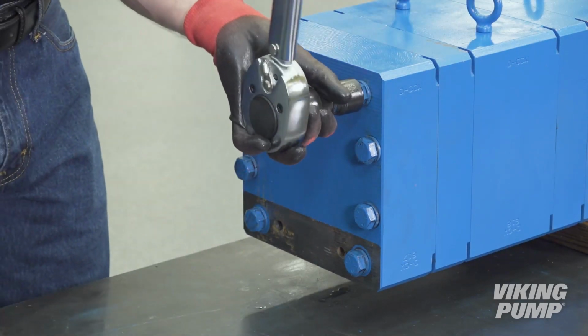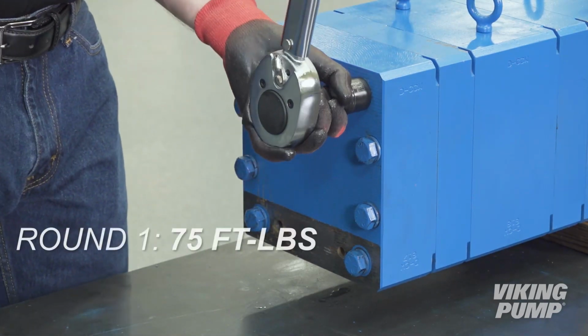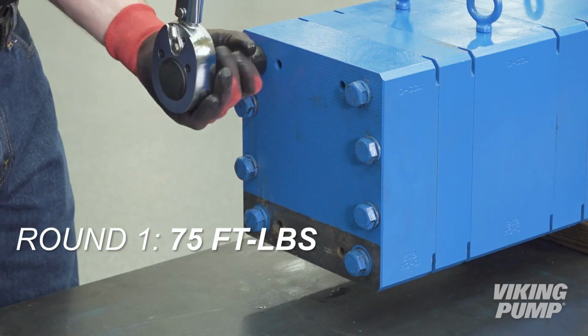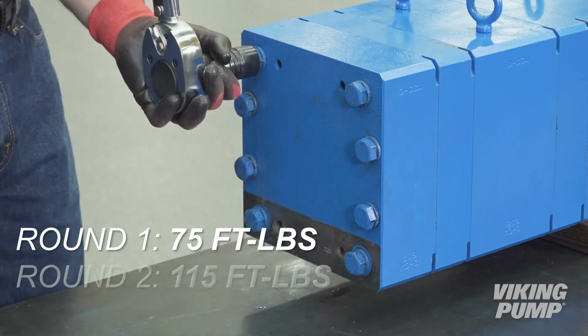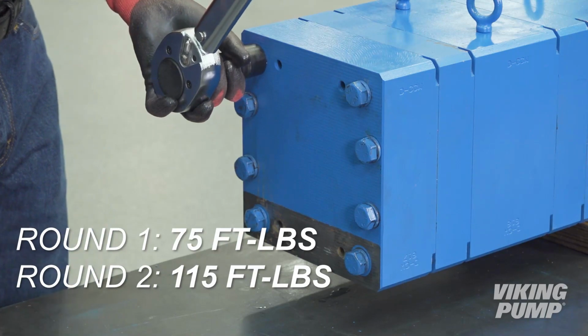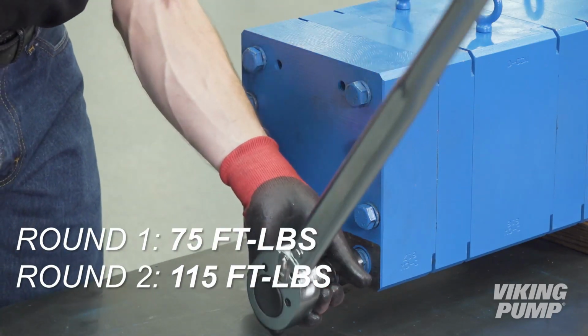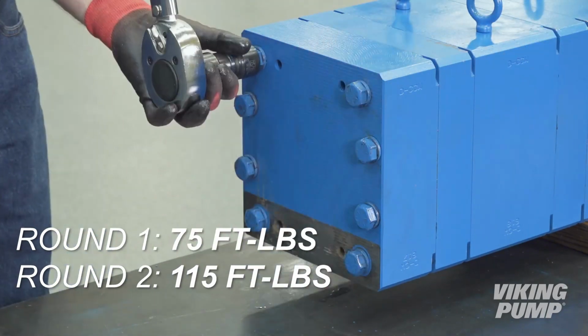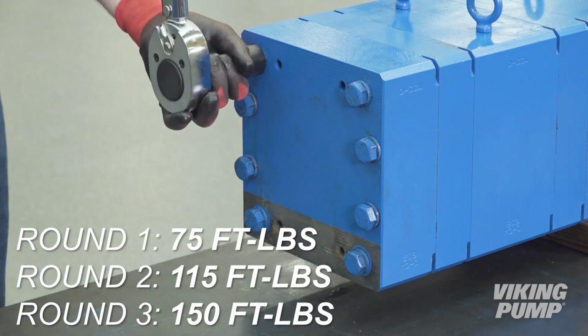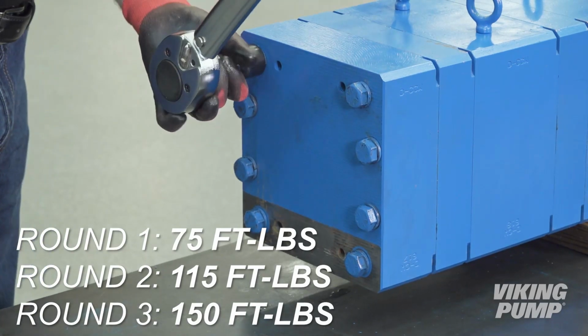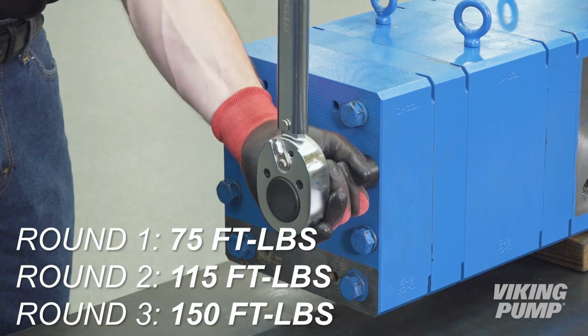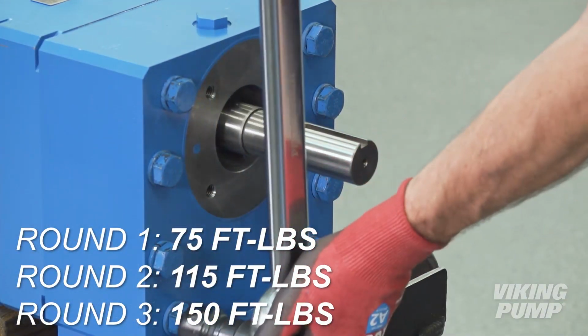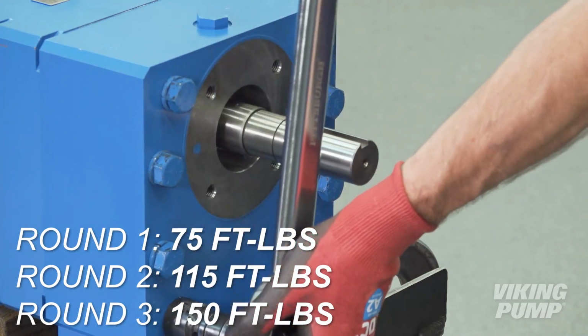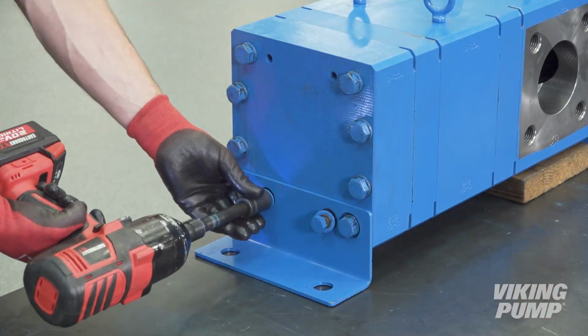The torque procedure involves 3 rounds. First, torque in a crisscross pattern to 75 foot-pounds. Next, torque to 115 foot-pounds in a crisscross pattern. And finally, torque to 150 foot-pounds in a crisscross pattern. Do this for both the head and bracket cap screws. Install the pump head mounting foot.